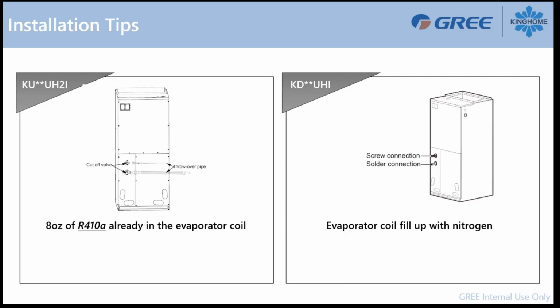Also, another difference between the KU and the KD air handler: the KU will have both screw connections, so on the liquid line and on the suction line. And the KD only has one screw connection. The other one, you have to braze the suction line.